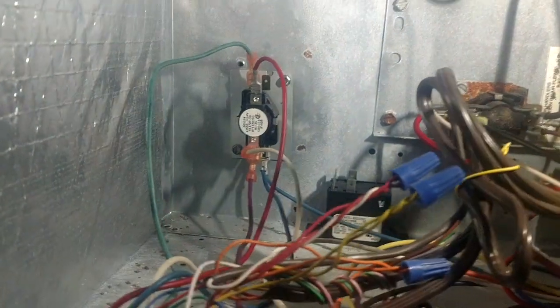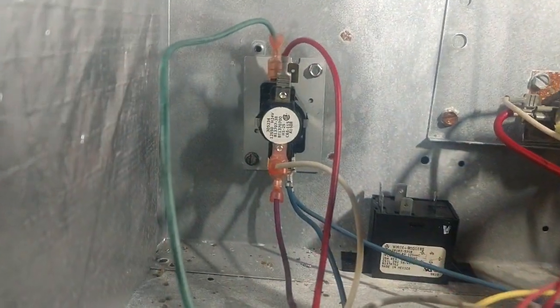It is a Goodman unit, and it is a good old X13 motor. So of course we have high voltage sitting on that motor all the time, and we're waiting on our low voltage to actually turn the motor on. And Goodman is using a relay to do that.